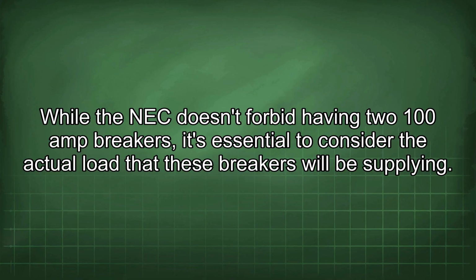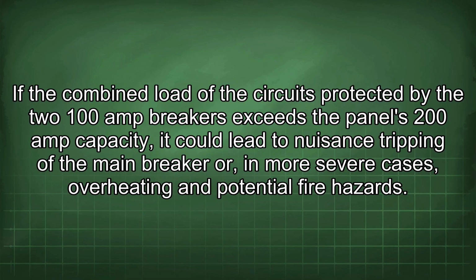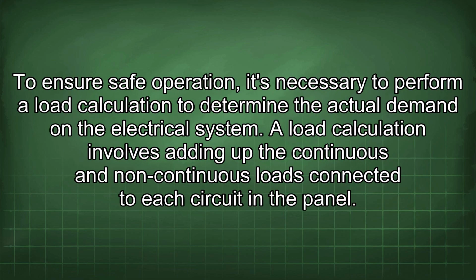breakers will be supplying. If the combined load of the circuits protected by the two 100-amp breakers exceeds the panel's 200-amp capacity, it could lead to nuisance tripping of the main breaker or, in more severe cases, overheating and potential fire hazards. To ensure safe operation, it's necessary to perform a load calculation to determine the actual demand on the electrical system. A load calculation involves adding up the continuous and non-continuous loads connected to each circuit in the panel.